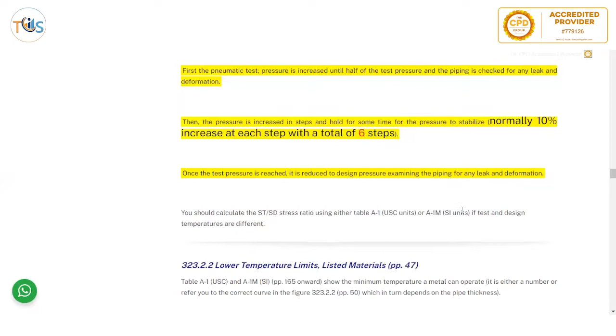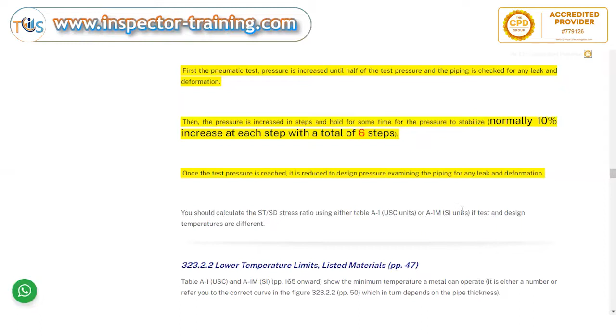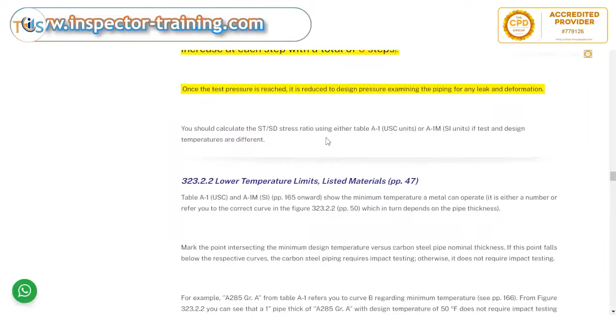So you have to reduce it by whatever the test pressure is, divided by 1.1. That would be the pressure that you will be checking when visually inspecting for pneumatic test, and divided by 1.3 during hydro test, and that would be the pressure you will be checking during hydro test. You should also calculate the ST-SD ratio using either table if test and design temperatures are different. This we already talked about.